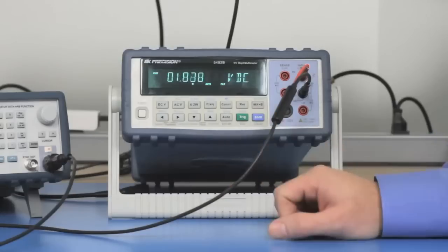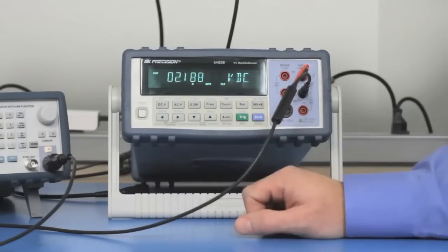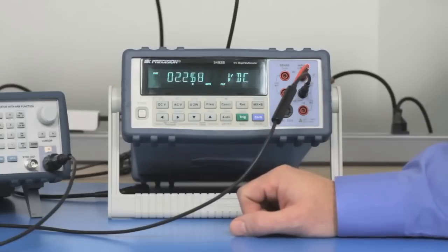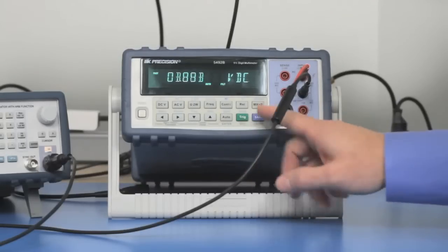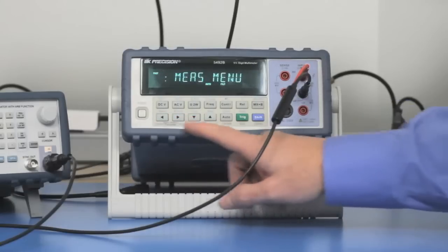As you'll see now, you're seeing all these readings. It's taking its measurements at 57 readings per second, and the asterisk is lit. As soon as the buffer is full, it will disappear, and we can go in and look at all of the values.